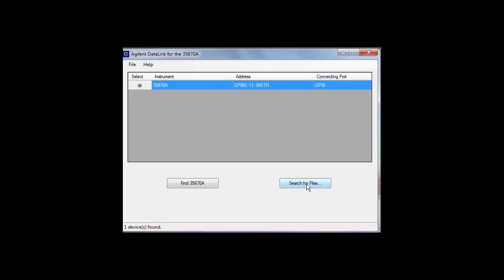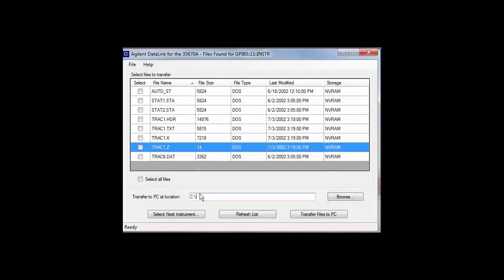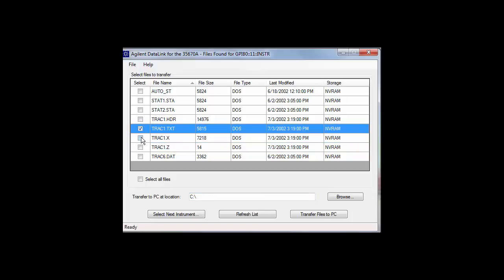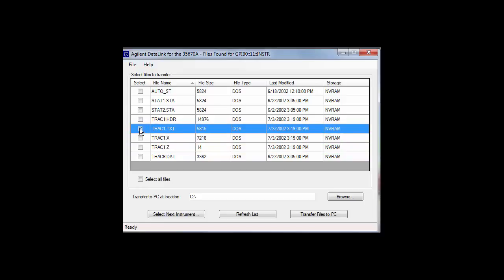Highlight the 35670A entry from which you want to download the files and click on the button labeled Search for Files. The software will search the instrument's non-volatile RAM, the RAM, and the floppy drive. The file names of the files which are found will be displayed in the window as shown. In this case, the software found eight files. You can then put a check mark next to the files you would like downloaded, put in the file path of the directory to which you would like the files to be saved, and then click on the Transfer Files to PC button.